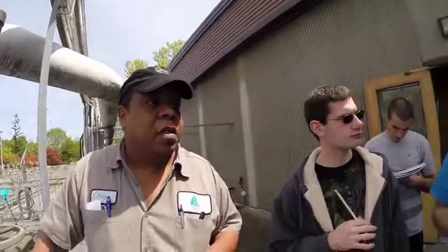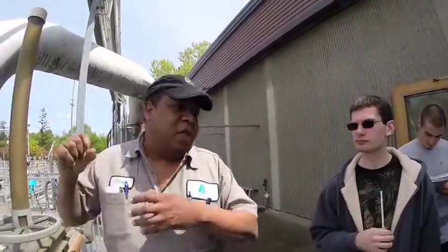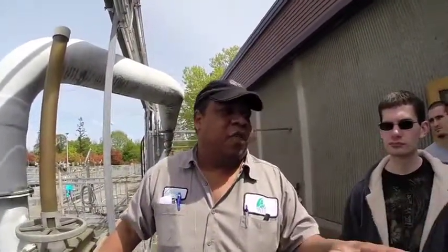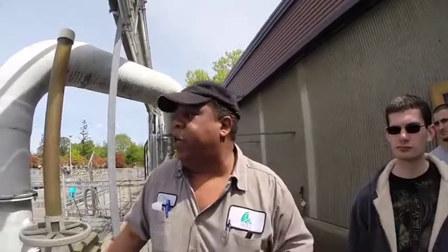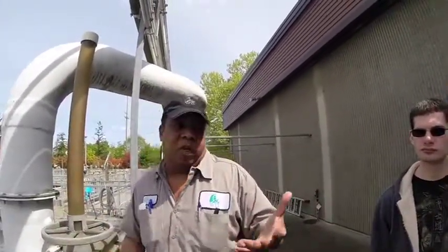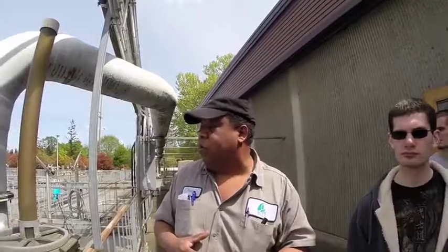What do you mean? Oh, the anoxic zones are for the odor? For odor and to make a different kind of bugs eat that before, because when the bugs come in, they're really hungry. So you just want them to eat everything that they can, because I don't want to get filaments. It's for filament control is what that's all about. That's why I run it this way, which seems to work.